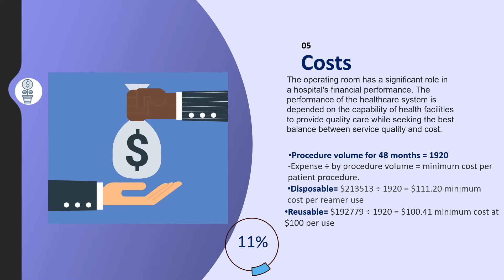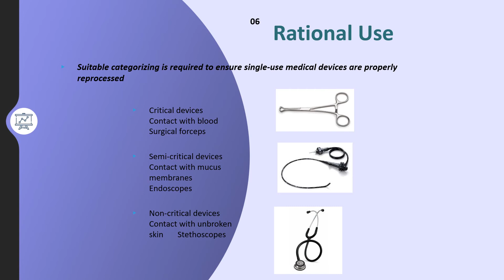I will talk about how to reuse single-use surgical devices rationally. So, they require categorization in order to receive an appropriate cleaning process. The reprocessing of such a device after it has been used must guarantee that they are sterile, properly functioning, and will not pose a potential risk to the patients who use it, depending on what they will contact, such as blood, mucous membranes, or skin. Devices can be classified as critical, semi-critical, or non-critical, as shown in the PowerPoint. In addition, in 2000, the FDA focused on this issue and released a document about requirements for the reprocessed devices, and we can use it as instructions.